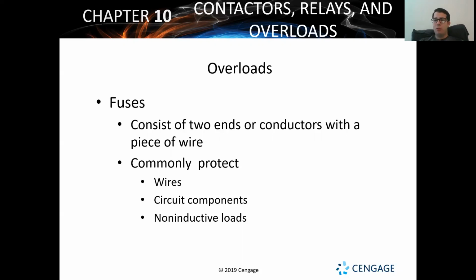Always double check a fuse. You can check it with voltage. If it's got power coming to it, it should read 0 volts across a fuse from one side to the other, because it's just going to let power pass right through it. It's not going to be a load of any kind. If you're testing with resistance, the only thing you need to test with is continuity. Y'all have it on your meters.